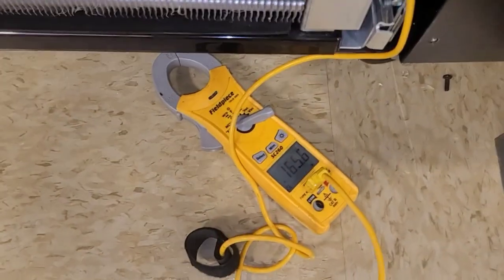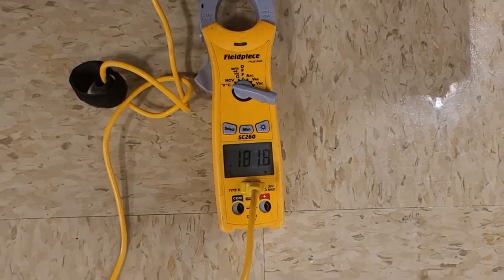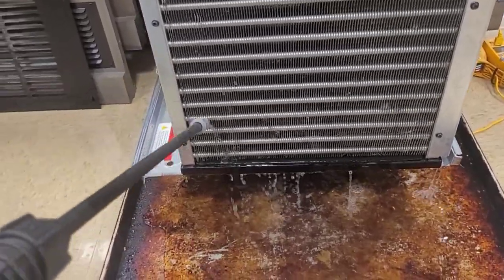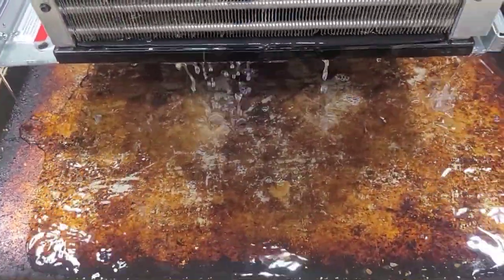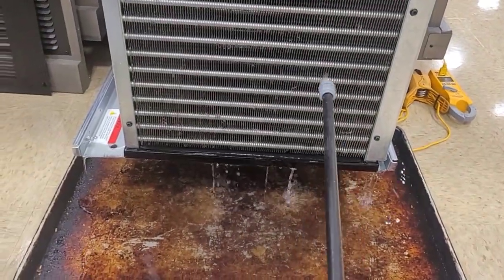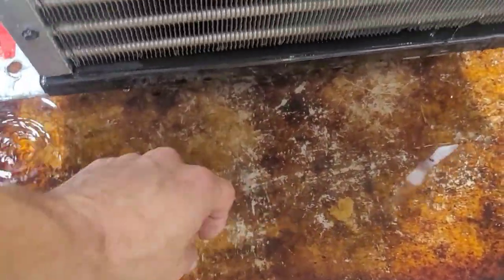It's cooling but we have a sight glass that's not fully liquid. What do you guys think about this design? I think it sucks. So I'm going to go find a pan to wash this thing. I don't really think this is going to do us any good because there's nothing even coming out, but I had to try. I rinsed it and like nothing came out.